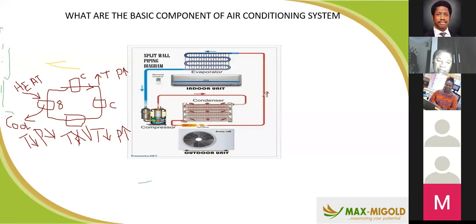After that, it goes into the thermostatic expansion valve, which reduces the pressure as I pointed out. When you reduce the temperature and pressure, you get what is called the refrigerating effect: a cool refrigerant where the temperature can drop as low as 7 degrees centigrade, while the heat within your building is around 28 to 30 degrees.